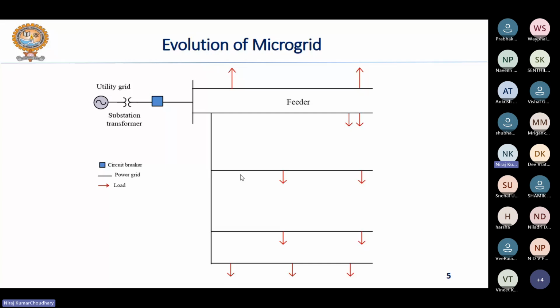Now in this slide, I will show you the basic evolution of the microgrid system. Here we can see a conventional distribution network where you have a radial feeder based system, and the only source of supply is the utility grid present in the system. So here the power flow is unidirectional in nature, starting from the utility grid and distributed towards the different feeders. So this is the structure of a conventional distribution system.